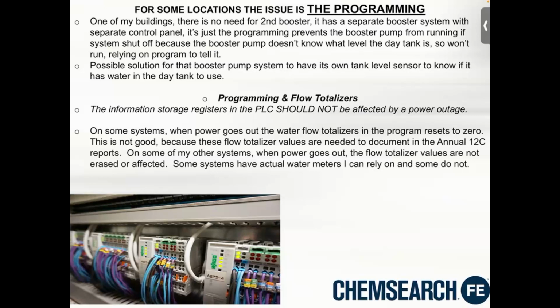I feel like the information storage registers in the PLC should not be affected by a power outage. What I mean by that is if a system loses power, say the building shuts off the power because they're doing tests on their elevators or fire or whatnot, then the water flow totalizers in the program should not reset to 0. But in some cases, it does happen in some of my systems. This is not good because these flow totalizer values are needed to document in, for example, San Francisco, the 12C report, and SFPUC uses these numbers to evaluate these systems. So it's not good when the system loses these values, because then nothing makes sense, basically.